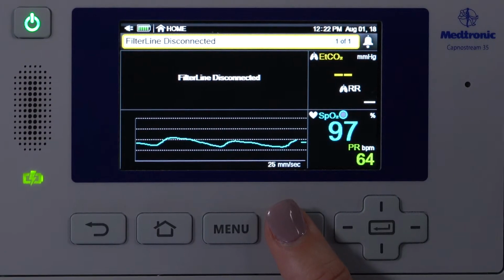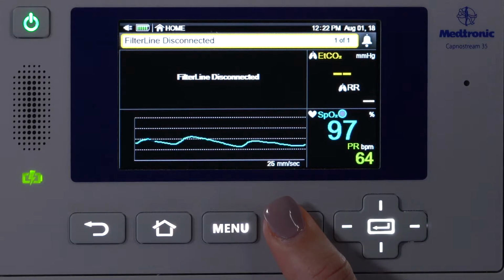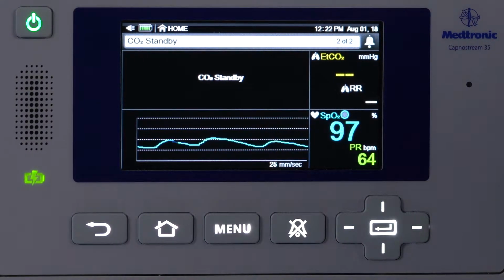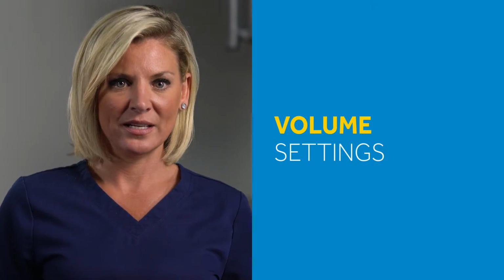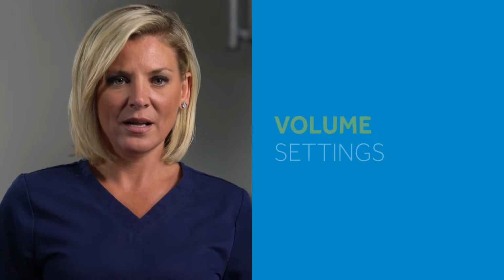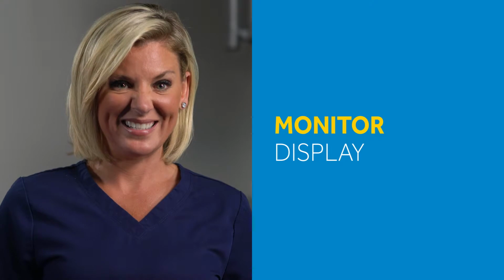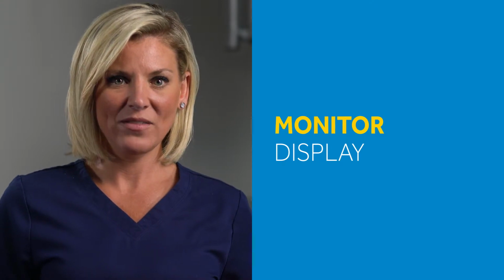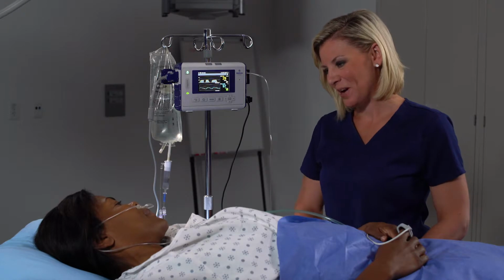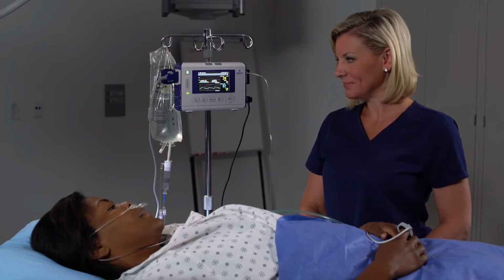Now the alarm silence button is important to understand and will be useful in your day-to-day workflow. Pressing this alarm silence button will suppress any audible alarms for 2 minutes. Please note, permanent alarm silencing in standby mode will need to be enabled within institutional default settings. The volume setting can be adjusted in the institutional default settings. The intuitive monitor is up and running in an instant. To set your baseline, have the patient breathe normally for 1 minute without talking. When the monitor is straight out of the box, the institutional defaults will need to be set by your facility.